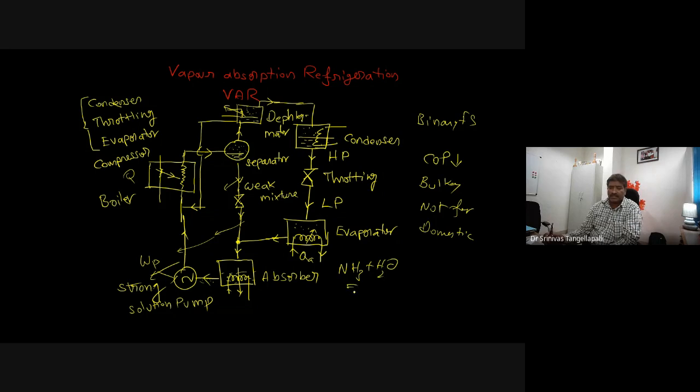You know the health problems of NH3: the smell, an increase in respiratory system issues. It's toxic in nature also. But environmentally it's fine. NH3 won't harm the atmosphere because there is no ozone depletion effect and no global warming effect of NH3. That's fine. But from the human body and respiratory point of view, NH3 is an issue.